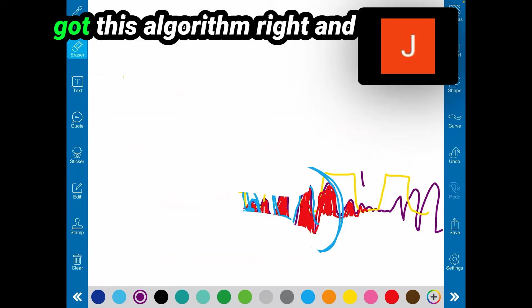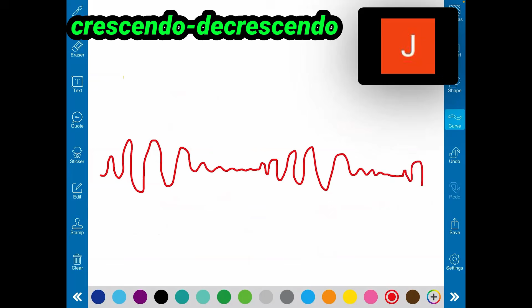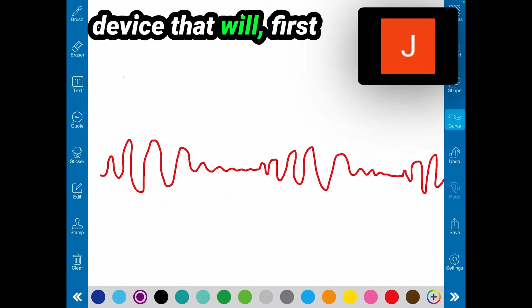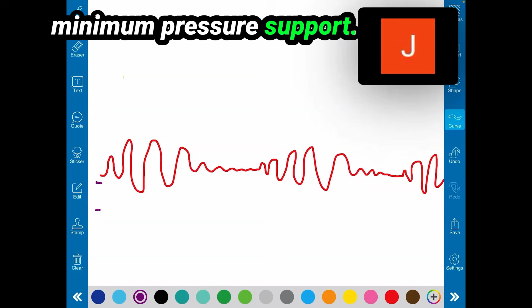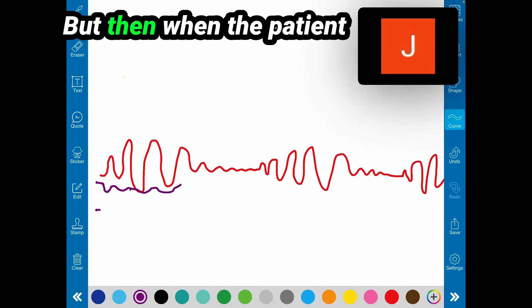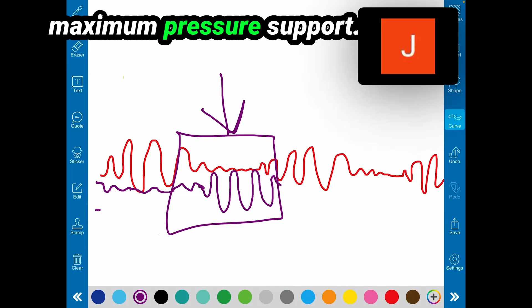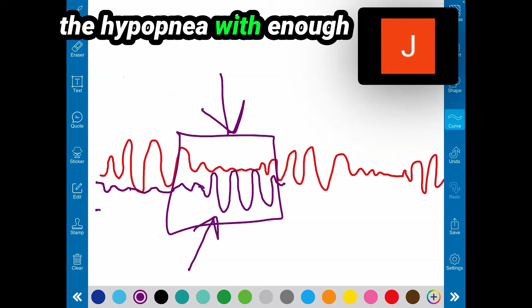Okay, good. Clear, siguro. Don't hesitate to ask. I want to make sure that you got this algorithm right and the idea behind this ASV. The reason why it works with some patients and the reason why it does not. All right. So if this patient is breathing this way, hypopnea central, crescendo, decrescendo, central, crescendo, decrescendo, central. How you fix this is a device that will, first of all, just have a minimum pressure support. Okay, minimum pressure support. But then, when the patient requires the necessary support, increase in ventilation, the device will increase, right, to maximum pressure support. So they will counteract the hypopnea with enough tidal volume, right?